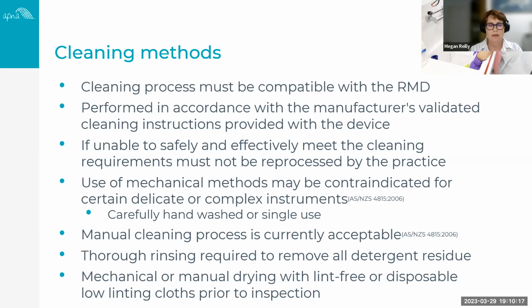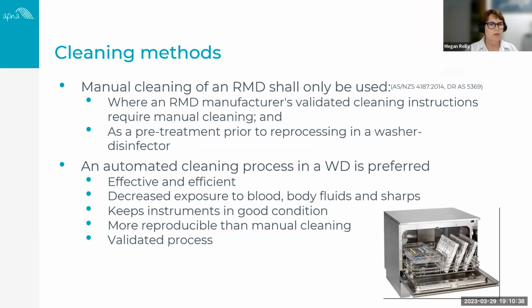And remembering that if we don't dry, that can actually increase the risk of contamination during inspection and assembly, if you do need to assemble your devices. Any residual moisture may impede the sterilisation process, and it can damage instruments as well, and instruments are costly. So in terms of our cleaning methods, manual cleaning of an RMD.